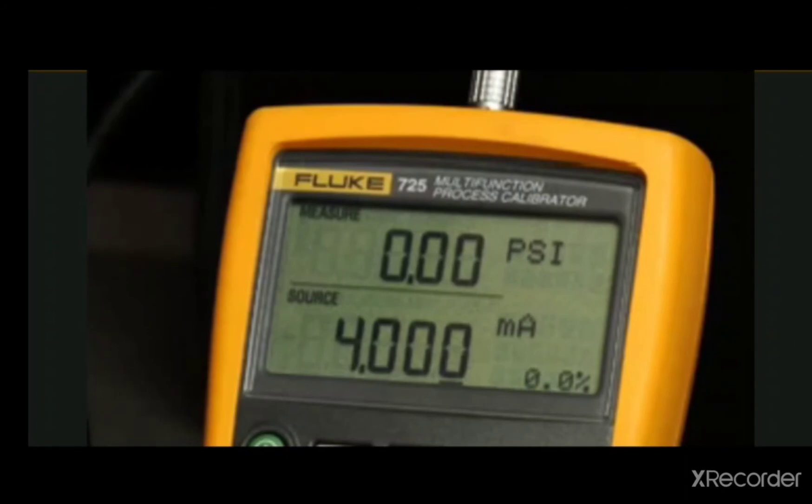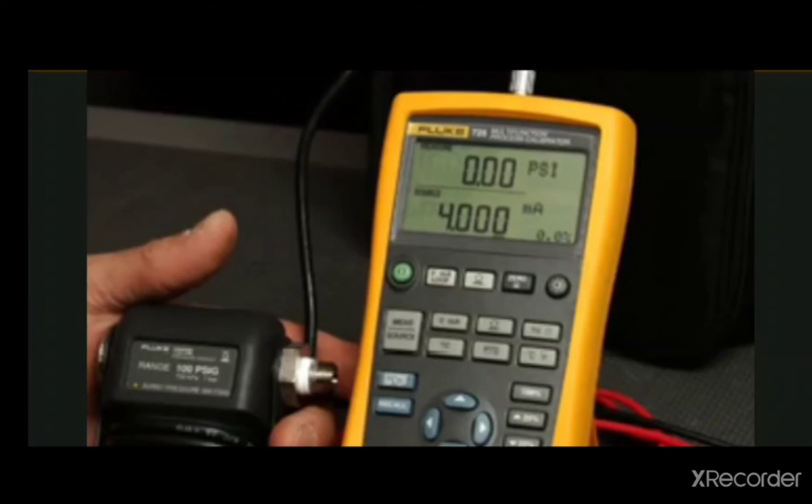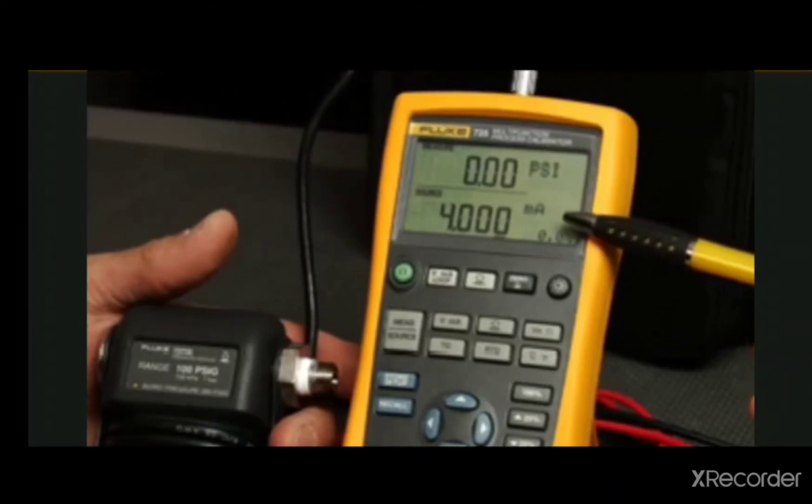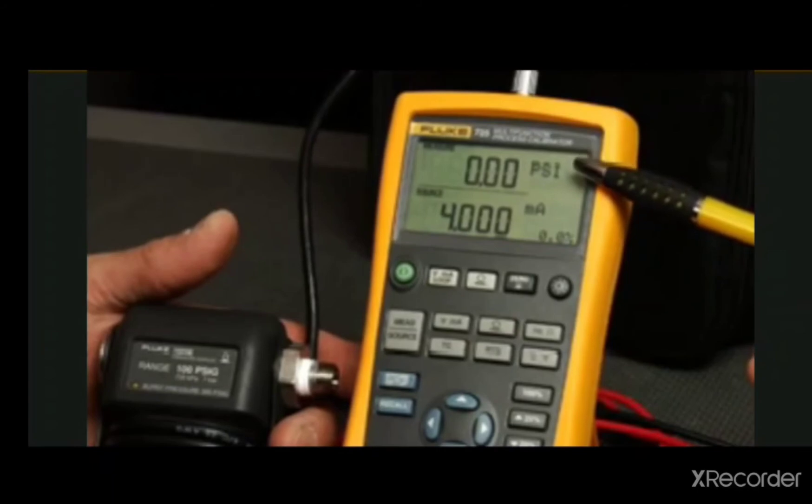Since the 725 has a dual screen, you can view both the input and output values applied to the transmitter or other process device being tested. For example, you can test valves, I2Ps, and view the milliamp value being sourced, as well as the milliamp or pressure on the output of the device simultaneously.